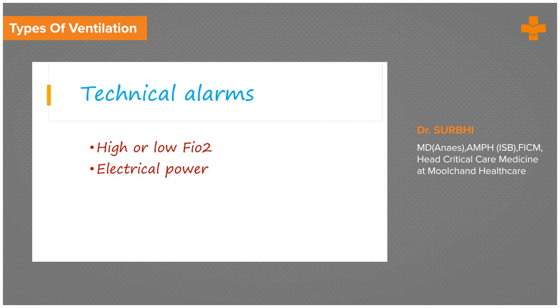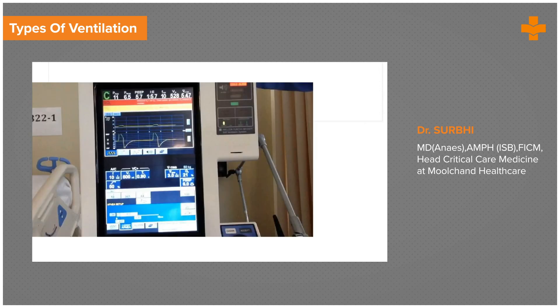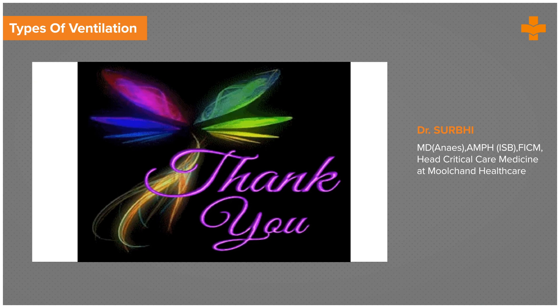Technical alarms, also called input alarms, include high or low FiO2 — a low FiO2 would mean there is no oxygen supply, and a high FiO2 would mean there is no air supply. Electrical power failure alarms are also inbuilt into the machines.